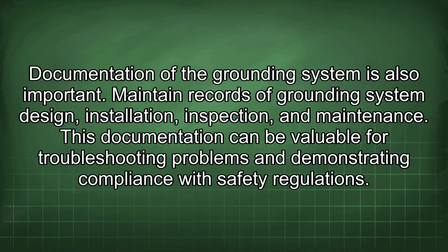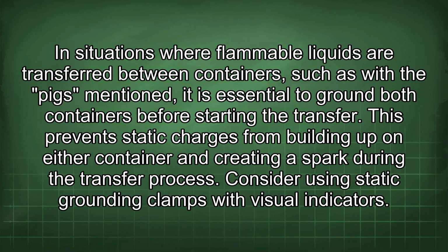Documentation of the grounding system is also important. Maintain records of grounding system design, installation, inspection, and maintenance. This documentation can be valuable for troubleshooting problems and demonstrating compliance with safety regulations. In situations where flammable liquids are transferred between containers, such as with the pigs mentioned, it is essential to ground both containers before starting the transfer. This prevents static charges from building up on either container and creating a spark during the transfer process.